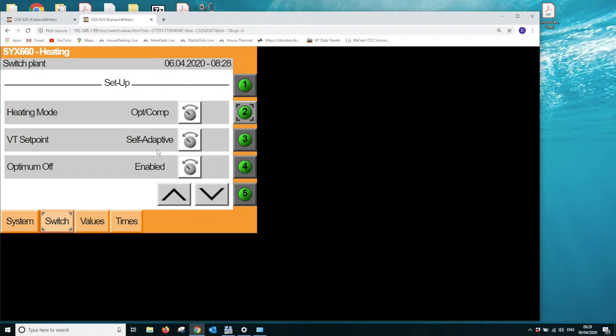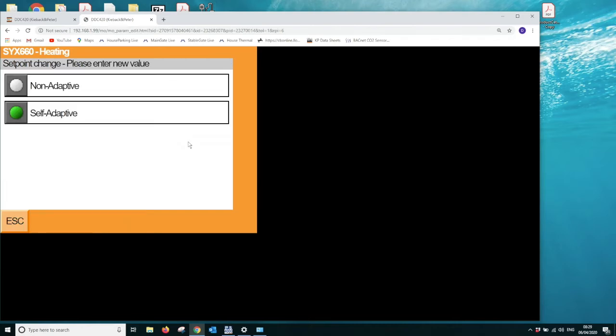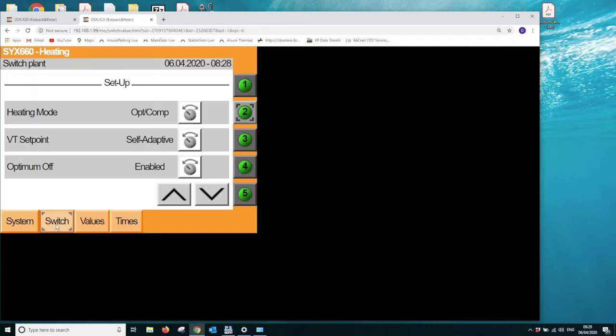And there is an adjustable ratio in the controller in the heating menu called room influence, where the default for that parameter would be 3 degrees. For every 1 degree you're below set point, you would increase the flow temperature by 3 degrees. Alternatively, if you were above set point, you can also reduce the flow set point as well, so that you have this live influence over the radiator temperature to try and affect some comfort and some better energy performance. Okay, so if you don't want room influence, you just select non-adaptive. If there are no room sensors available, then it will become automatically inactive.